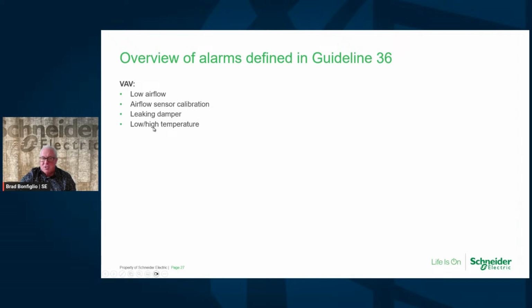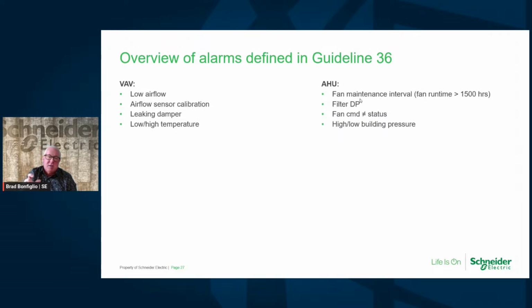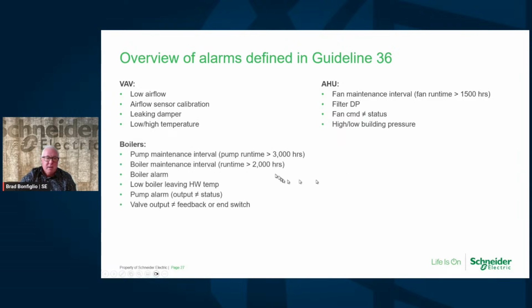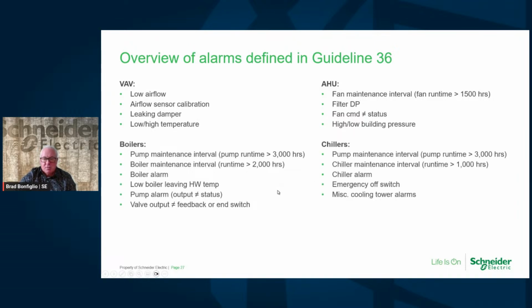So you've got different alarms in here for the VAV, the air handler, boilers, and chillers, and what each of these mean and how they're defined within the guideline. I'll show you later why these are important, because we must standardize the naming of these and define them ahead of time if we're going to do fault detection. A lot of these relate back to semantic tagging. If you don't set up your naming standards ahead of time, how are you going to be able to measure or affect those points if you don't know the standards?